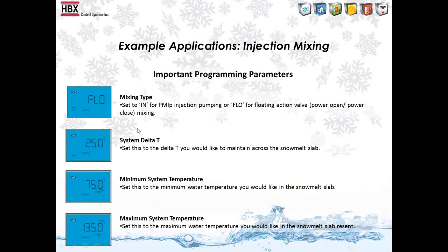So in this case you would set your mixing type to FLO. Obviously we can have a system delta T in there as well at 25. So what the system delta T does is makes it so that you're not cracking the slab. You don't want to put 135 degree water to a slab that is sitting at only 25 degrees, because you would have basically a 110 degree delta T and you'll end up with big cracks in your concrete. So that's something we want to avoid, and that's why people put snow melt systems in.